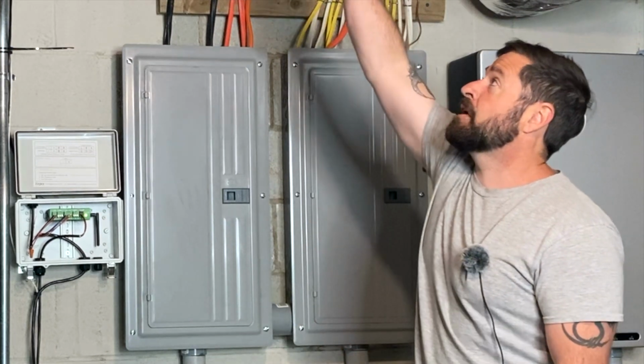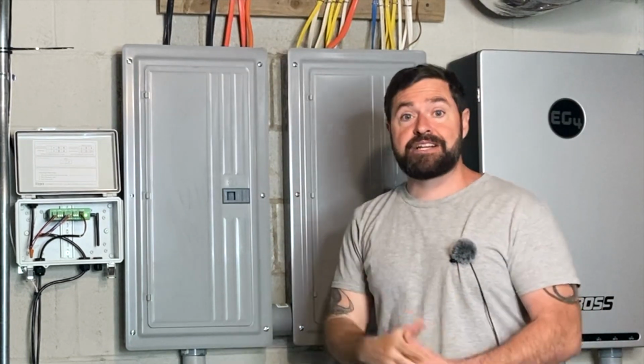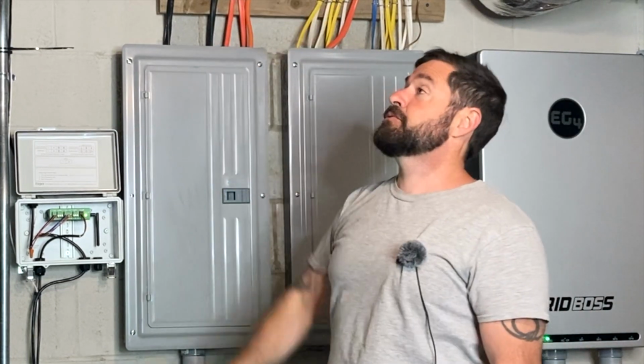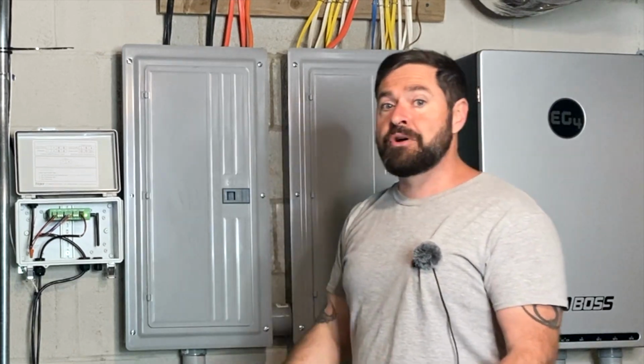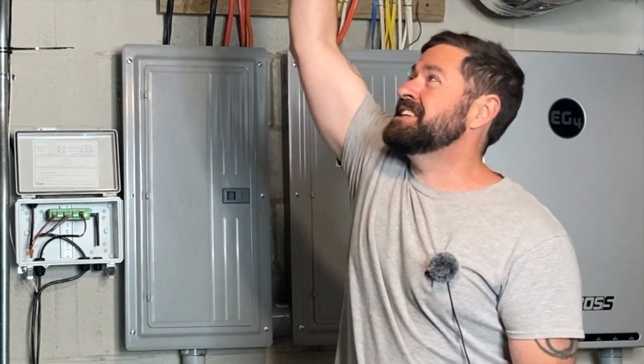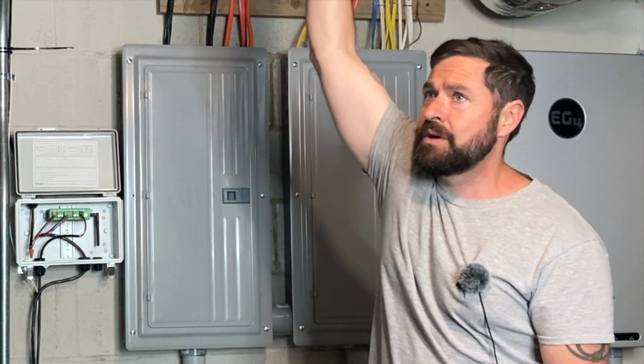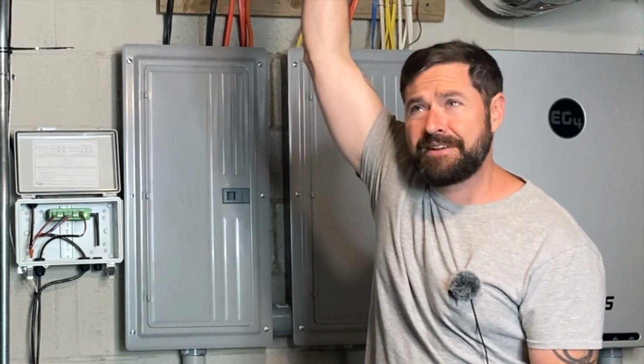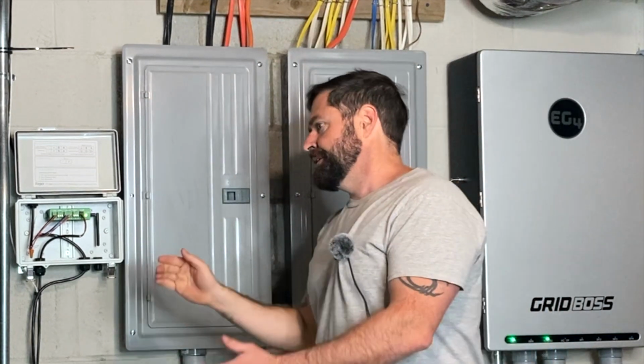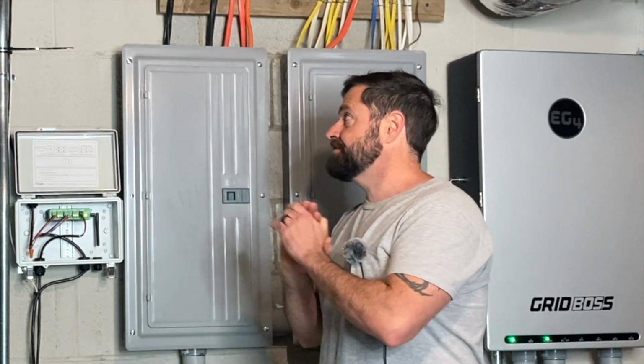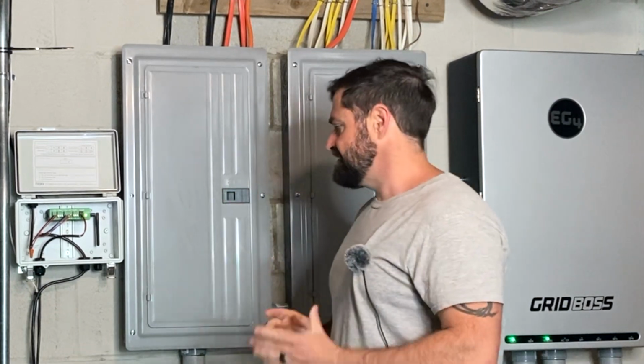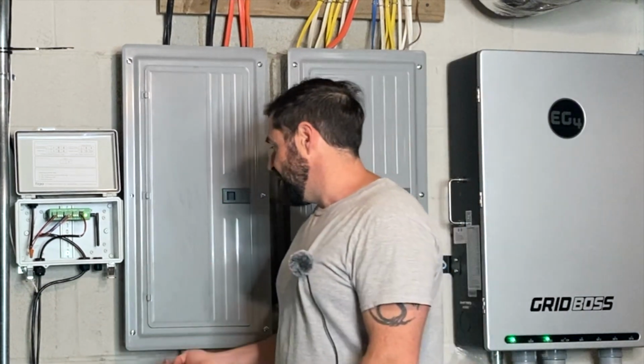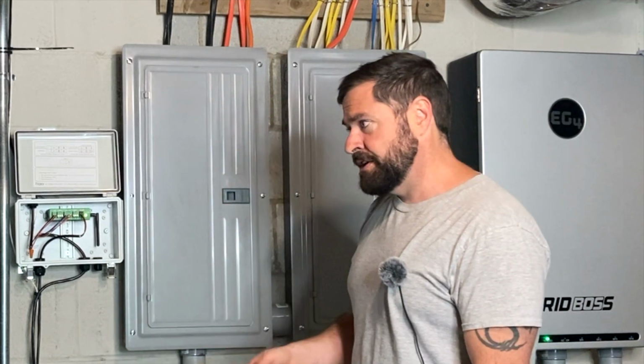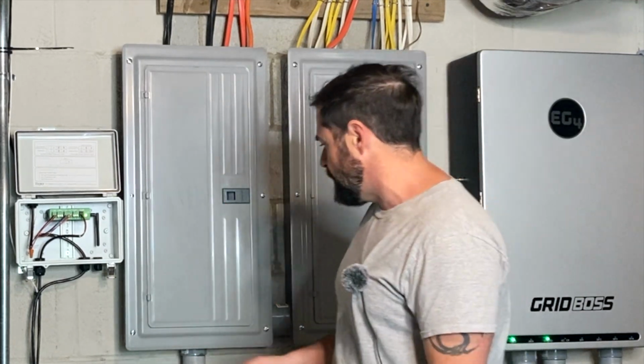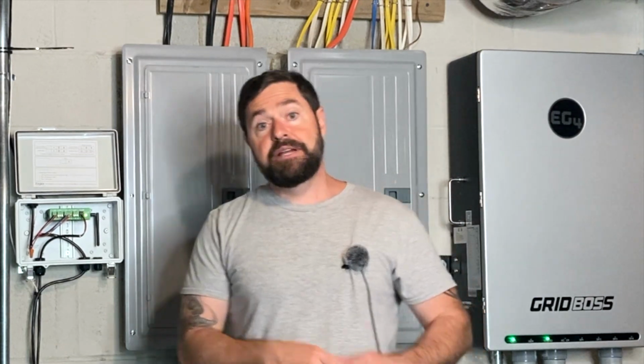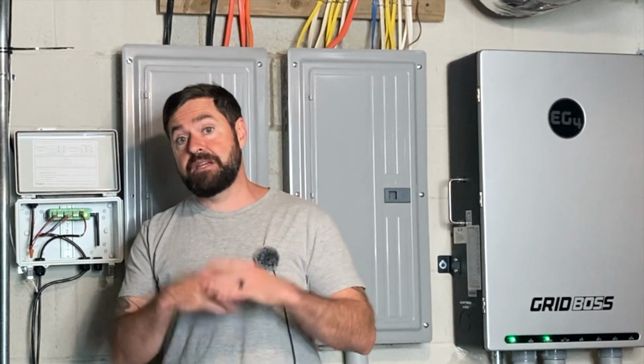Any wire or conduit has got to be supported per the National Electric Code. So Romex, it's like every 3 feet. Flexible conduit, most of it's every 3 feet. EMT, at least 3/4 inch, once every 10 feet, or I think 3 feet from a termination. Little things like that -- get all your stuff strapped, secured, stapled, labeled. If you have any knockouts busted out that were unused, you need to plug those with a knockout cover. If it's outside, that knockout cover's got to be watertight.